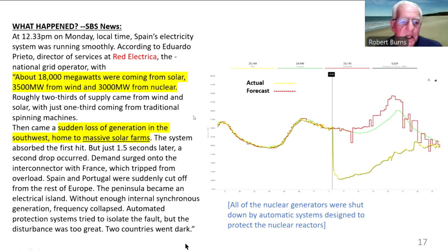Anyway, there was a sudden loss of generation in the southwest, and it's the home to all those massive solar farms. One farm tripped and the system absorbed it, but then 1.5 seconds later, a second drop occurred when another wind solar farm tripped. Demand surged onto the interconnector with France, which tripped from overload. Spain and Portugal were cut off from the rest of Europe. The peninsula became an island without enough internal synchronous generation.